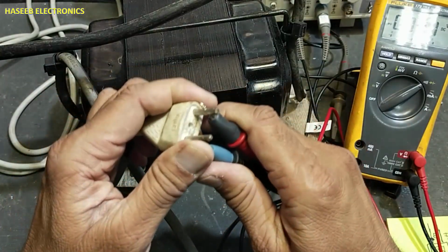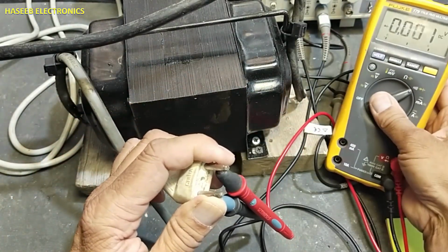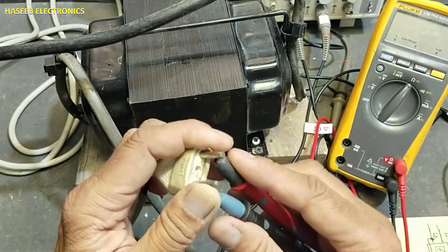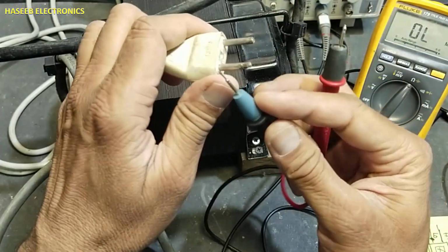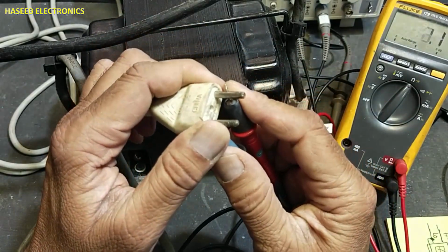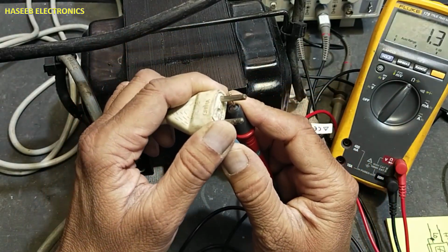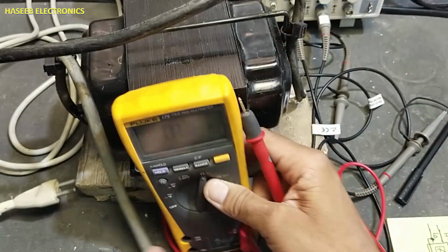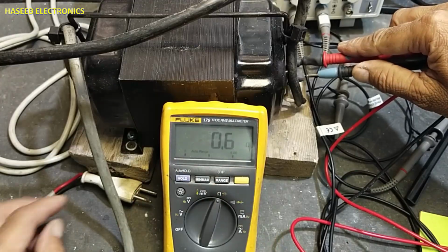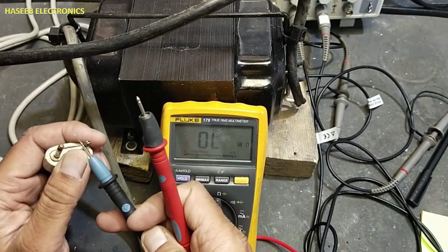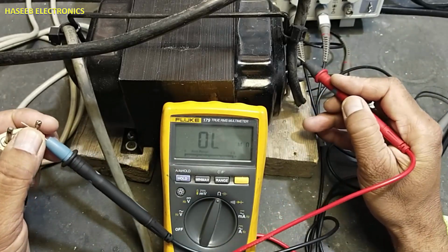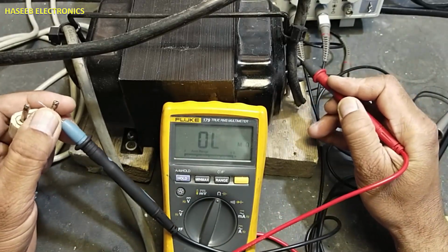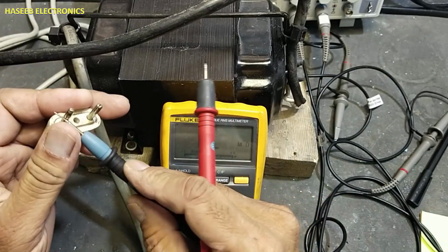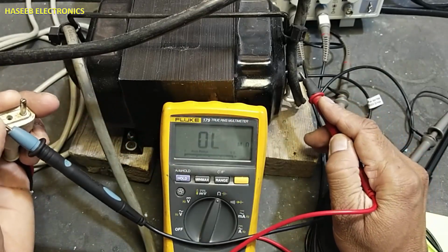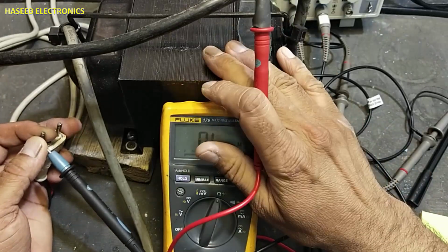On the primary side, it has approximately 1.4 ohms, and if we test the secondary, it is 0.6 ohms. If we test the isolation transformer with the primary, the secondary terminal must show an open circuit. So this is our isolation transformer.